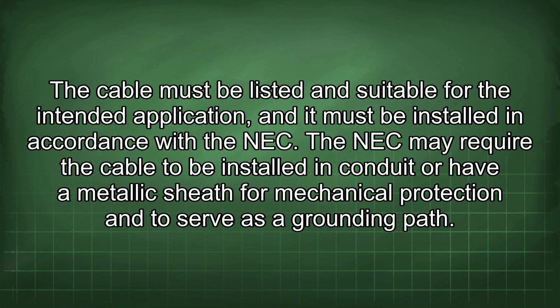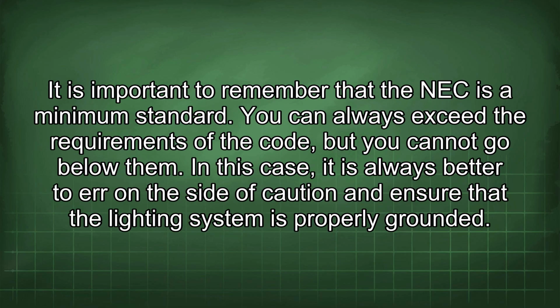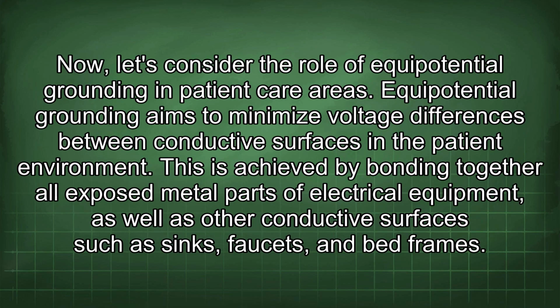The cable must be listed and suitable for the intended application, and it must be installed in accordance with the NEC. The NEC may require the cable to be installed in conduit or have a metallic sheath for mechanical protection and to serve as a grounding path. It is important to remember that the NEC is a minimum standard. You can always exceed the requirements of the code, but you cannot go below them. In this case, it is always better to err on the side of caution and ensure that the lighting system is properly grounded. Now let's consider the role of equipotential grounding in patient care areas.